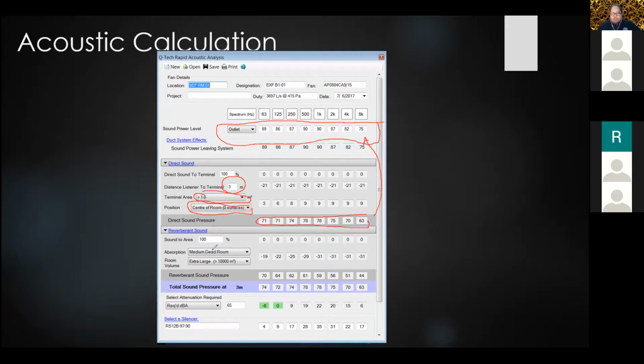sound power level. Then you need to input whether it's a dead room or what kind of absorption; there are some choices. Then the volume of the room will of course affect it: if the volume is small, the sound doesn't disperse, and if the volume is large, the sound disperses, right? And then here is the recommended silencer, and this is the decibels it can decrease from your fan sound power level.